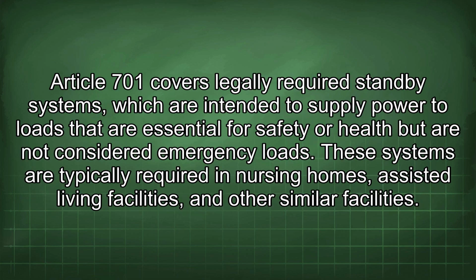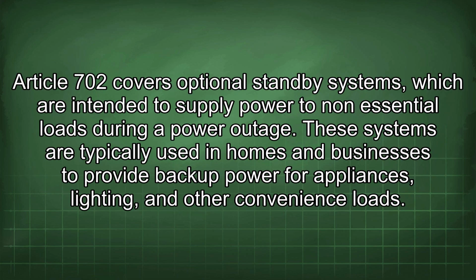Article 701 covers legally required standby systems, which are intended to supply power to loads that are essential for safety or health but are not considered emergency loads. These systems are typically required in nursing homes, assisted living facilities, and other similar facilities. Article 702 covers optional standby systems, which are intended to supply power to non-essential loads during a power outage. These systems are typically used in homes and businesses to provide backup power for appliances, lighting, and other convenience loads.